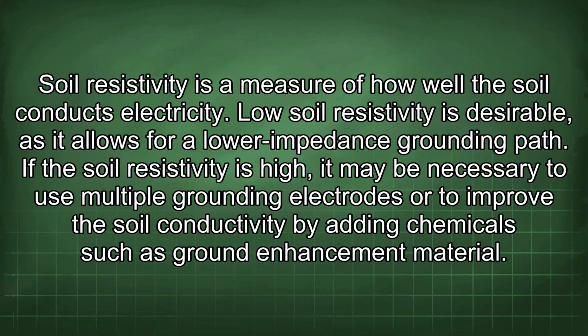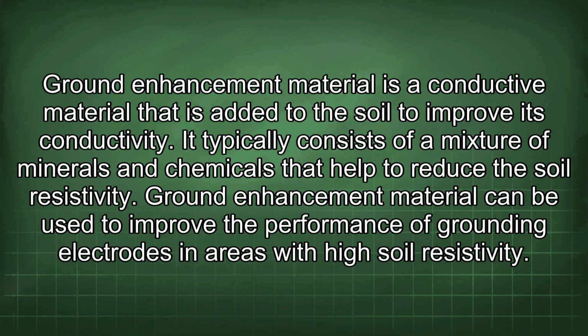If the soil resistivity is high, it may be necessary to use multiple grounding electrodes or to improve the soil conductivity by adding chemicals such as ground enhancement material. Ground enhancement material is a conductive material that is added to the soil to improve its conductivity. It typically consists of a mixture of minerals and chemicals that help to reduce the soil resistivity. Ground enhancement material can be used to improve the performance of grounding electrodes in areas with high soil resistivity.